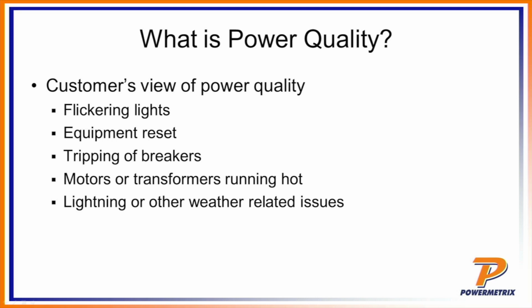Tripping of breakers. If you're having surges, that could cause that, and that obviously is something else the customer's going to have a lot of trouble with. They have to dig out the flashlight and go find the fuse box to get things put back into service. If that happens on a consistent basis, they're going to be aggravated by that. Something you might see in an industrial setting would be motors or transformers running hot. A lot of times that's caused by harmonics. We're going to talk about that quite a bit today. And then finally, lightning or other weather-related issues. Those are very intermittent problems, but nonetheless you get a lot of energy during a lightning surge, and so that can cause a lot of big problems.